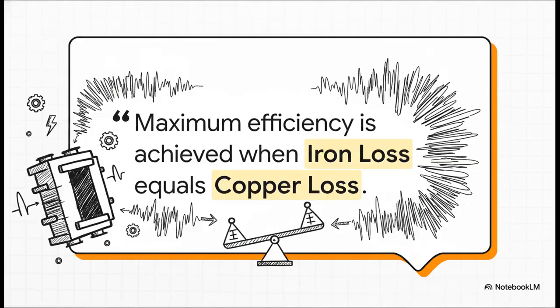It's huge. So is there a point where a transformer is working at its absolute best? Yup, there's a sweet spot. Remember the constant iron losses and the variable copper losses? A transformer hits peak efficiency at the exact moment those two losses are equal, a perfect balancing act between its two types of imperfections.